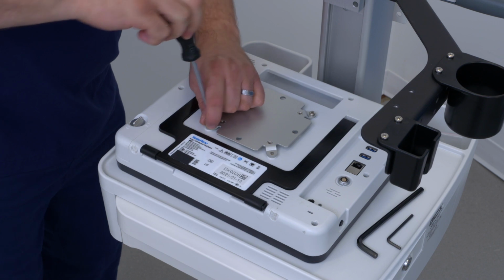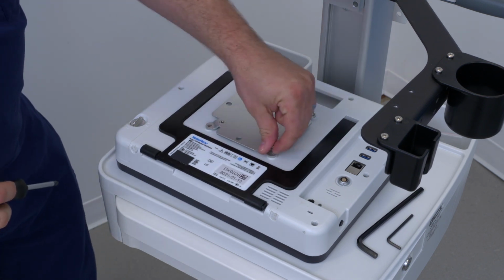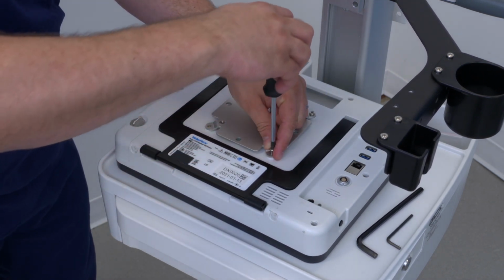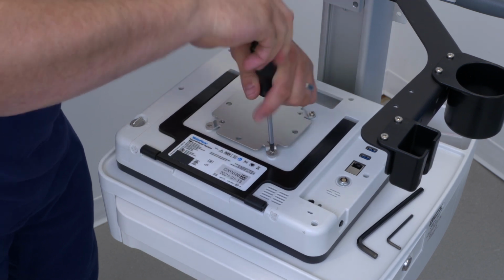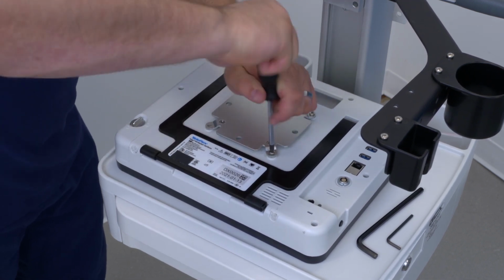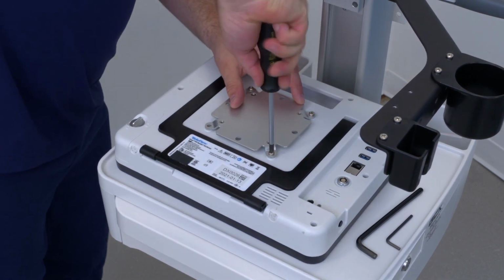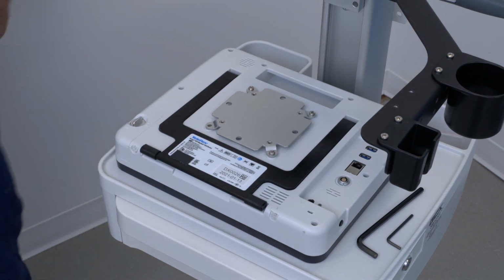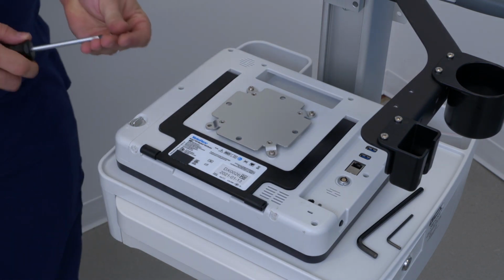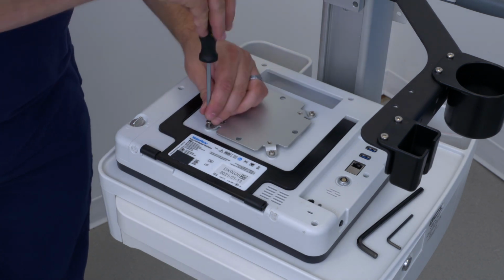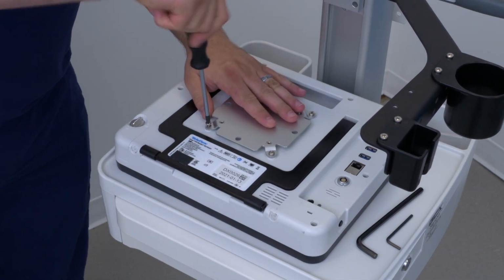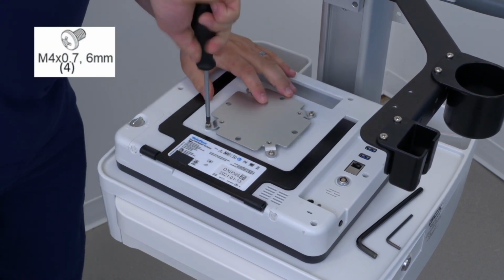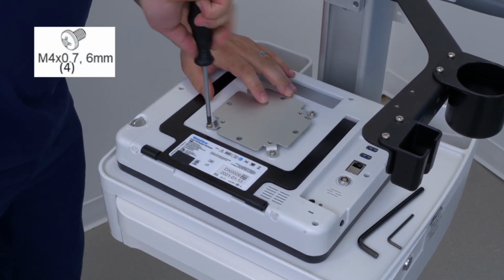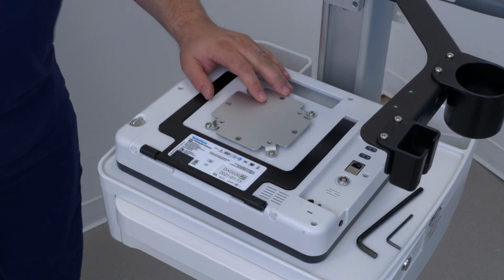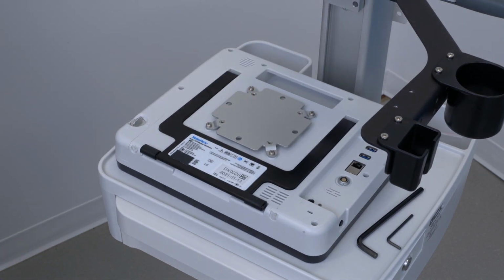The VPS Rhythm DLX device monitor has a 100 by 100 mm spacing VESA configuration. The cart flush mount is 75 by 75 mm. A 75 to 100 mm VESA adapter plate is included with both the RHY 100 Cart A and the DLX 200 arm. Attach the adapter plate to the back of the VPS Rhythm DLX device monitor using the 4 M4 by 0.7 6 mm screws. Do not over-tighten as you may damage the monitor.